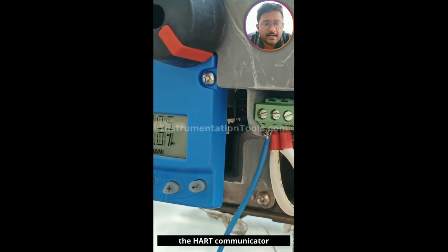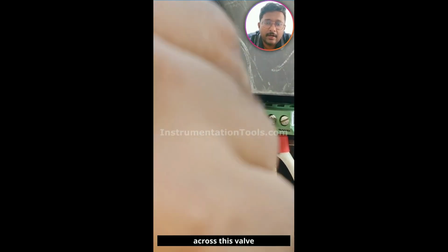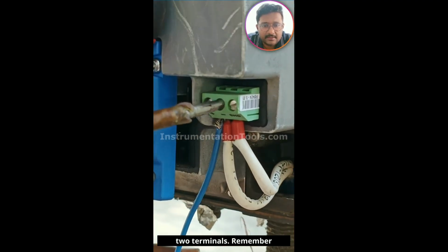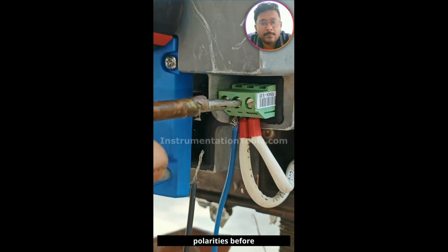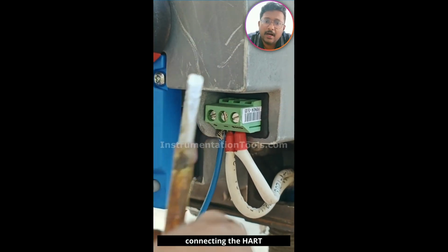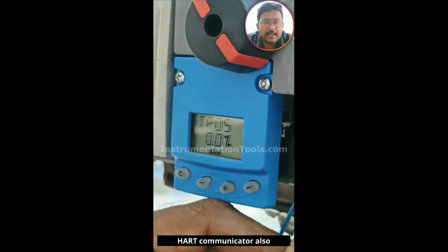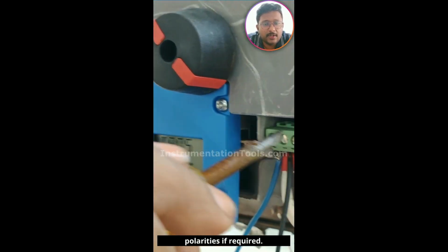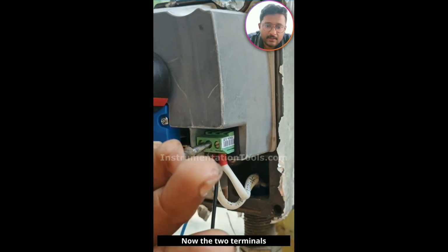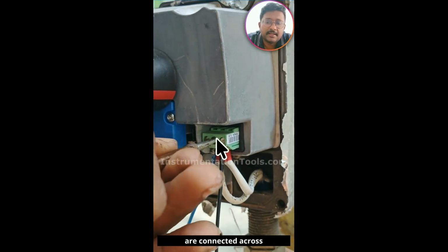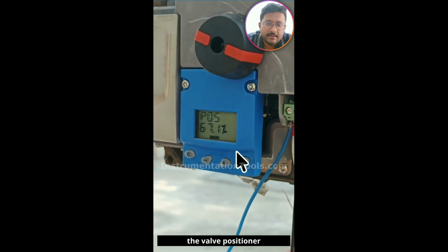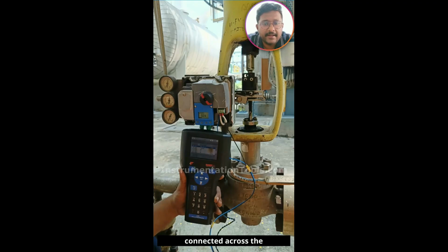Okay. Now we are connecting the HART communicator across this valve positioner's 2 terminals. Remember, you must check your polarities before connecting the HART communicator. After connecting the HART communicator also, you can change the polarities if required. Now the 2 terminals are connected across the valve positioner. So the HART communicator was connected across the 2 terminals of the valve positioner. In the next video, we will discuss this HART communicator and its inside parameters.